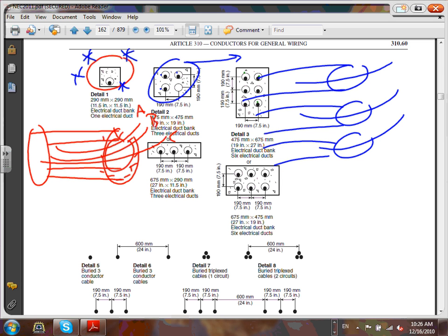The other thing is ease of installation. Installing 1 multi-conductor cable is easier, not much easier, than installing 3 cables, right? Because you're installing 3 cables. So that's one application. That's why they allow you to go to different sizes if you can't fit them in a duct, underground. And these are underground ducts. Underground ducts, guys, are not conduits. I can make an underground duct, not 4-inch, a 1 foot diameter duct underground, and pull my cable in it. These are not conduits. These are underground ducts. You can custom design any ducts. What's the size of these? They have a size somewhere on them. They have the distance between them, 7.5 inches. But what's the size of the ducts? Most of them are 5 and 6 inch ducts underground, but you can get an 8-inch duct diameter.